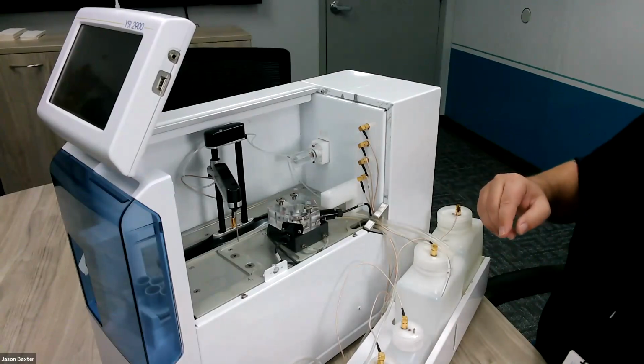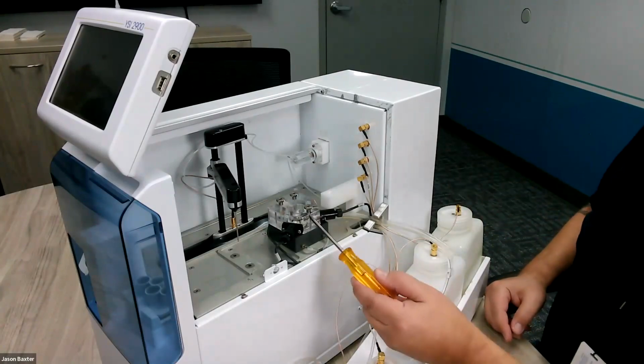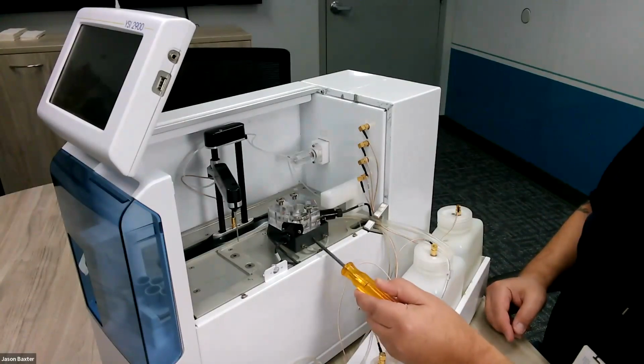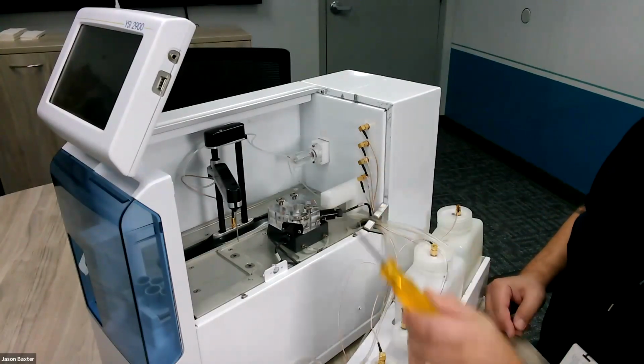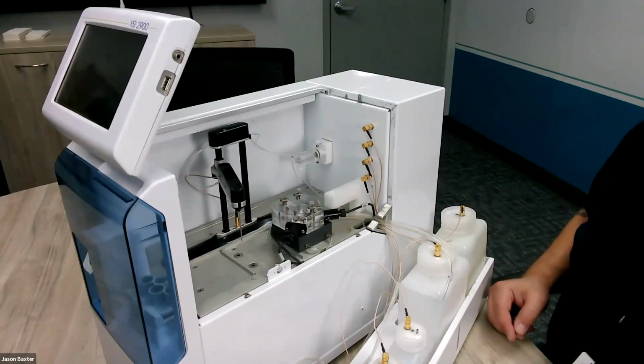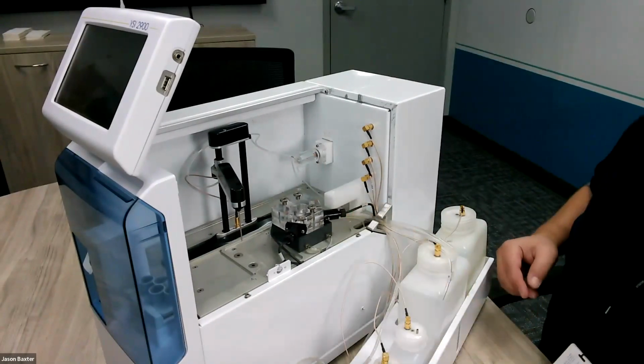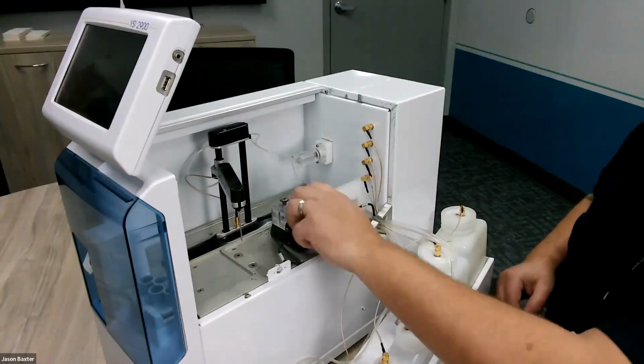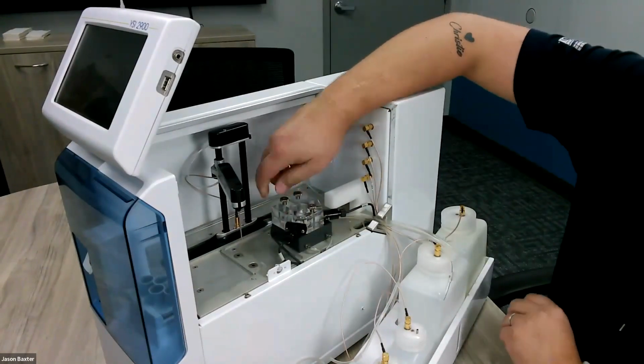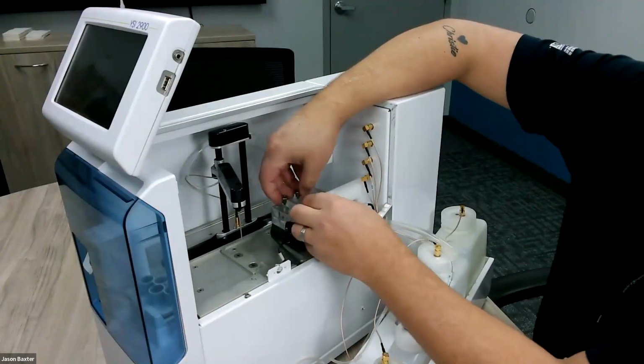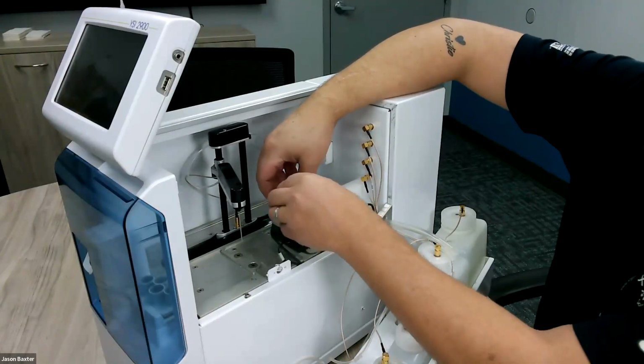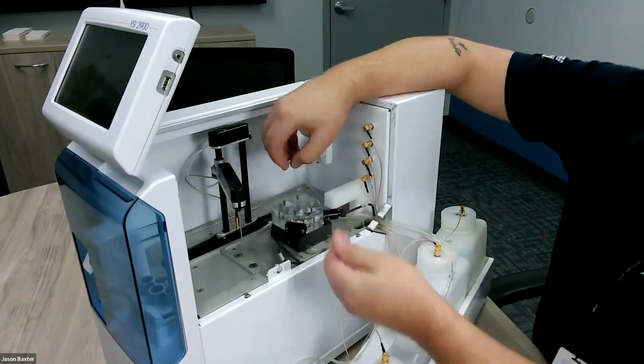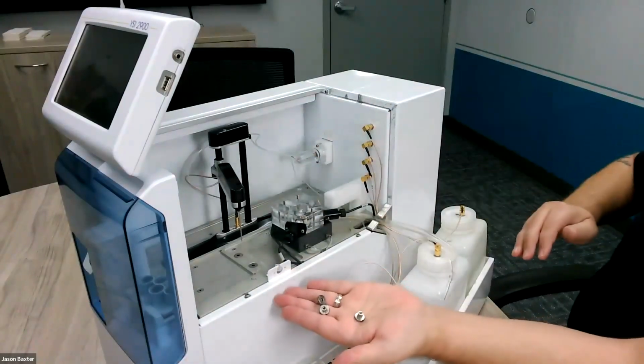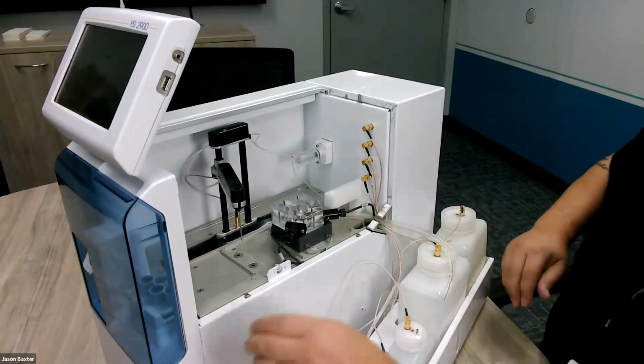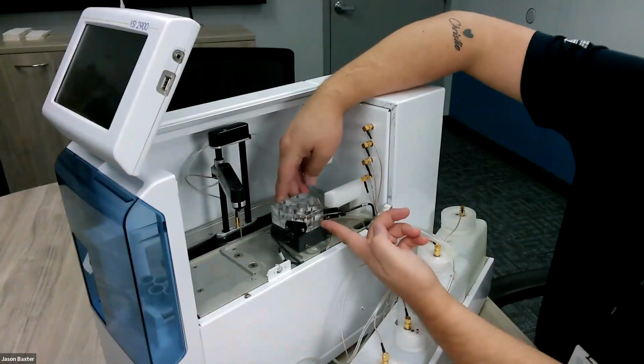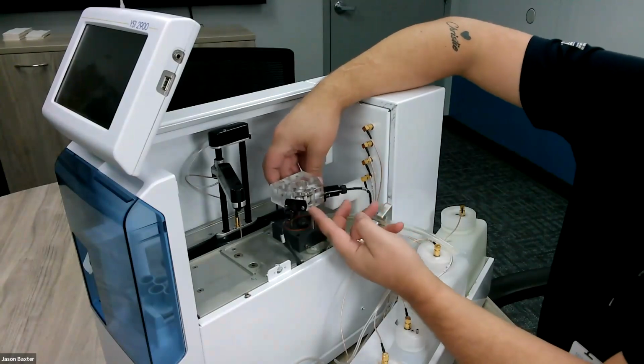And now what I want to do is remove the sample chamber, the waste chamber, and the sipper pump housing. To do this, you're going to need your 3/32 Allen wrench. Start by removing your 3 thumb screws on the top. All 3 thumb screws are the same, so there's no reason to worry about which one goes where. Remove these 3, set them to the side. At this point, you can lift the sample chamber up, the clear component. It will lift up and off.